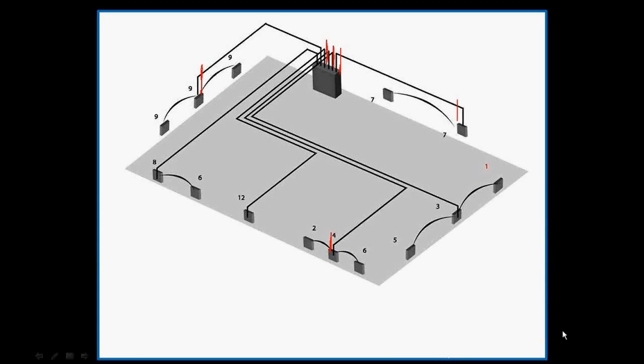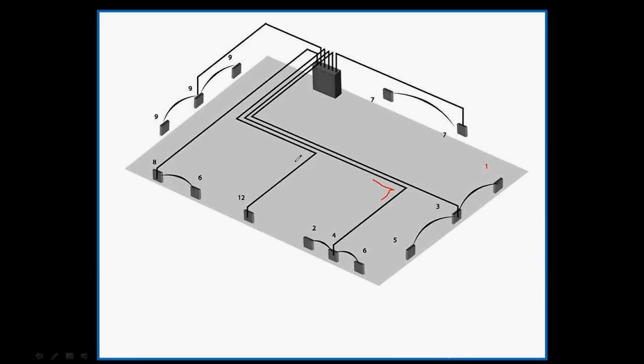Now we'll consider the 90-degree elbows or 90-degree bends. You do not take off elbows for branch circuits. This is one difference between takeoff for branch conduit and takeoff for feeder conduit. Branch conduit elbows are field bends, so you do not count them or enter them into Red Rhino.